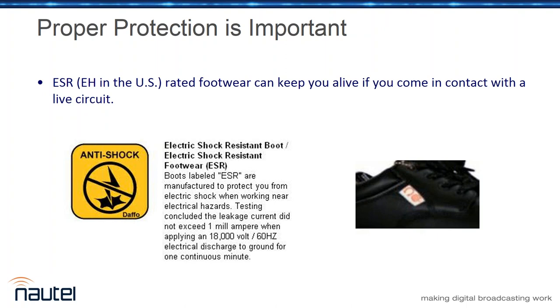So one of the requirements we have here at Nautel for anybody working on live electrical equipment, or any electrical equipment at all, is that if you're in our test room, you need a pair of shock-resistant footwear. Whether it's EH rated for the US, or ESR, electric shock resistant, the CSA standard in Canada, the standard's the same: they'll handle 18,000 volts across the sole without passing more than a milliamp of current. These shoes can make the difference between getting a bad shock or not even noticing, or noticing a tingle when you could have had a significant burn.